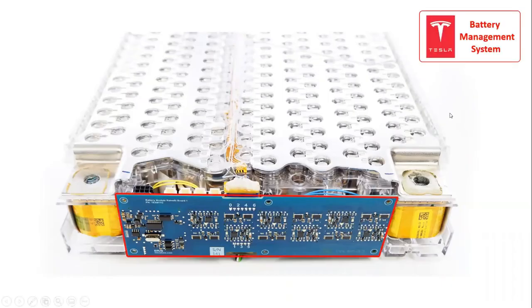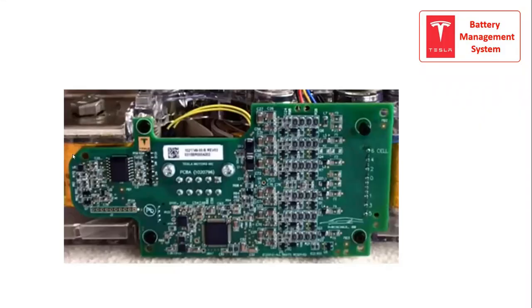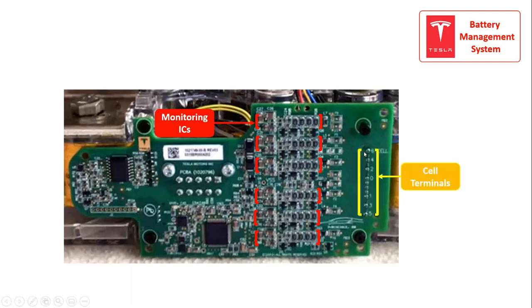Battery Management Systems (BMS) is the most important component in a battery pack, essential for battery pack safety. The BMS used by Tesla in Model S is based around the Texas Instruments BQ76PL536AQ1, a 3 to 6 series cell lithium-ion battery monitor and secondary protection. The red encircled area of the BMS shows that it contains 6 monitoring ICs for each series connection in the module. The yellow encircled area shows the terminals where the connection from the 6 cells will be connected. The IC by TI used in the BMS can be daisy-chained to need only one communication connection to the system. The BMS is integrated into every module and monitors the battery life, temperature, and charge-discharge cycle of cells.